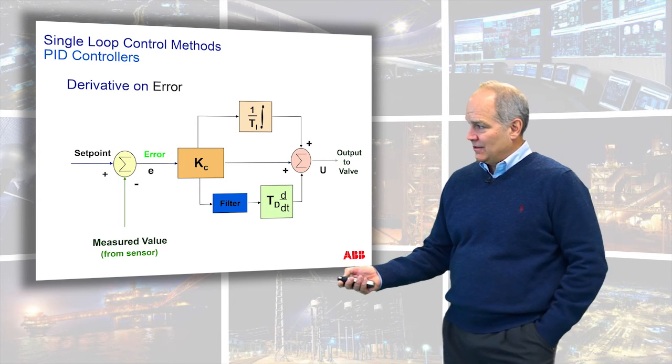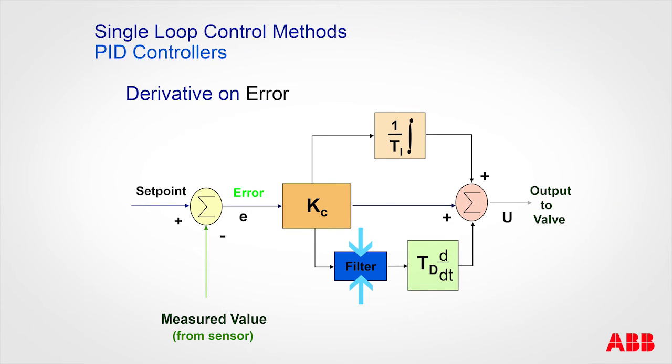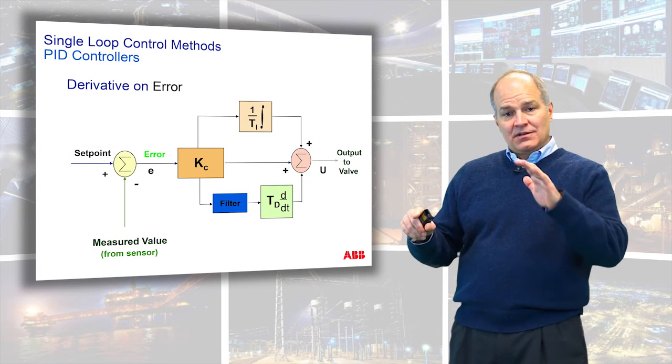And it would look like this. So you'd have a little derivative filter that comes in and so that you're filtering the signal to try to get the noise out, to get the signal characteristics. In other words, you're wanting to slow the measurement down. That way the prediction can work a little better.